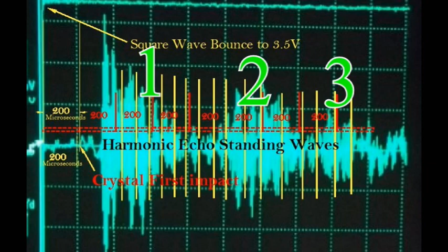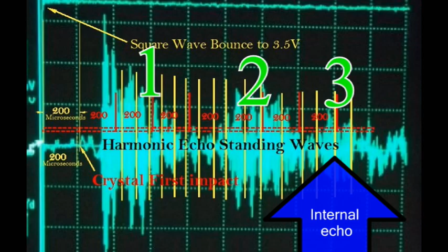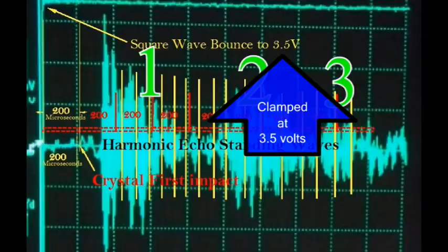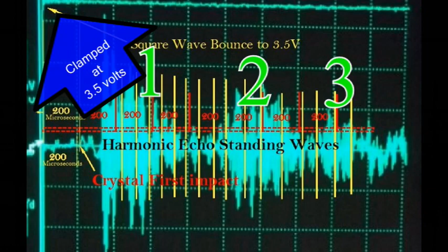The crystal has an internal echo, front to back, inside the wafer itself. These are the many waves you see. They fire back into the bar and head back to the front end where they bounce and return. Each approximate 200 microseconds is an echo. Successive echoes combine into the complex wave. You can see 3 prominent groups as they diminish over successive trips across the bar. Remember, every 200 microseconds is a 1 meter trip across the bar. It is 400 microseconds for a round trip. With each pass, the transmitter, which is clamped at 3.5 volts, still responds and adds its own internal resonance.